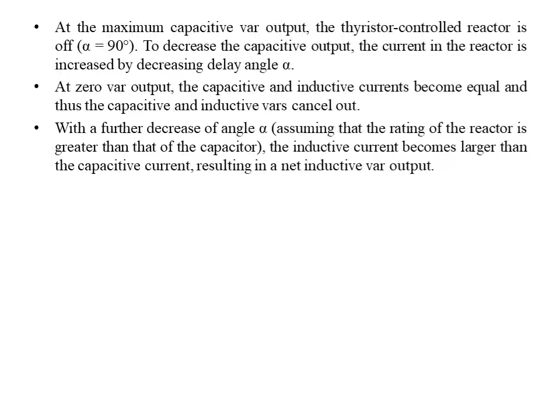And the third condition is when I decrease alpha in such a way that the thyristor controlled reactor produces maximum current, that is, the inductive current is maximum as compared to the capacitive current. Then the net resulting reactance or VAR generation will be inductive VAR output, that is, the maximum VAR generation will be from the thyristor controlled reactor side.